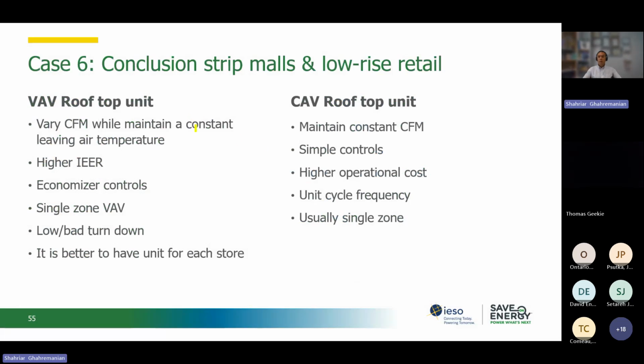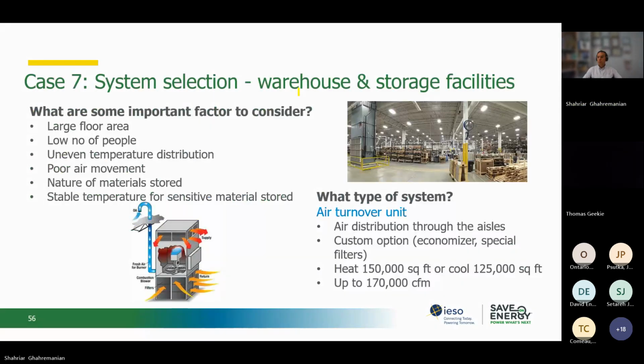There is a possibility to consider VAV rooftop units versus constant air volume. The VAV is a little bit more expensive because it's variable air volume, so the CFM of air can differ based on the air temperature that they want to have in their area. But again, its efficiency is much higher, and that's a good one to consider. They are a little bit more expensive than the CAV, constant air volume RTUs, but it's good to be considered as well. The other example is about warehouses and storage facilities. Again, in storage facilities we typically have a large floor area, and there are many spaces with no people or a low number of people in them.